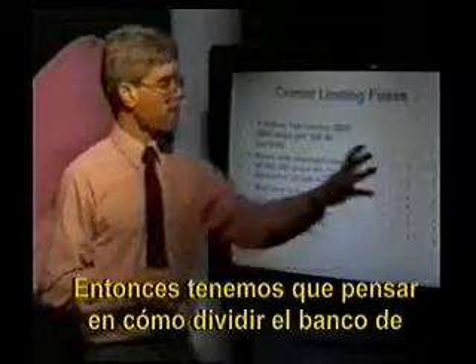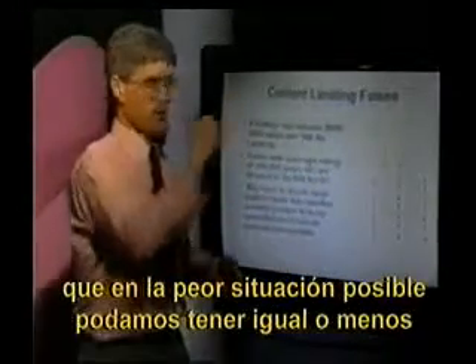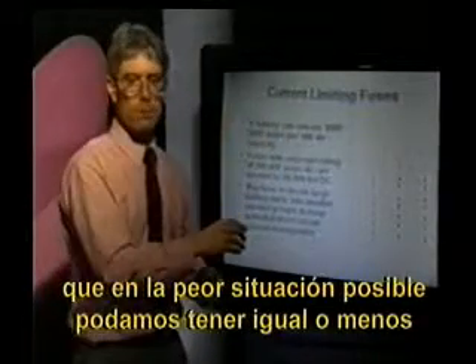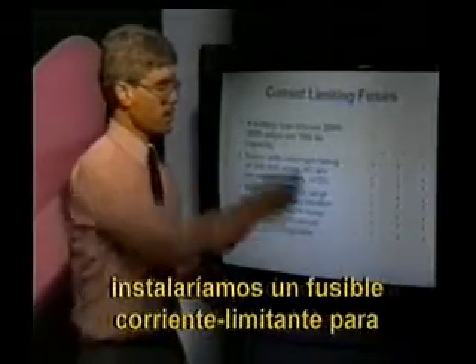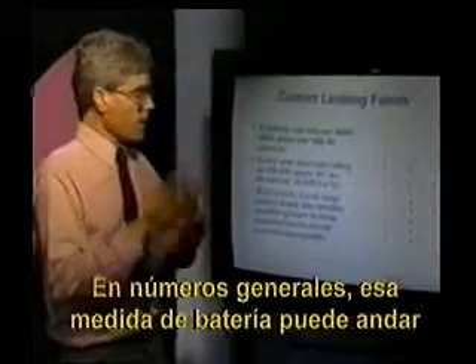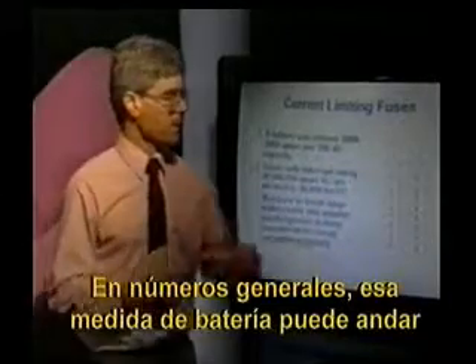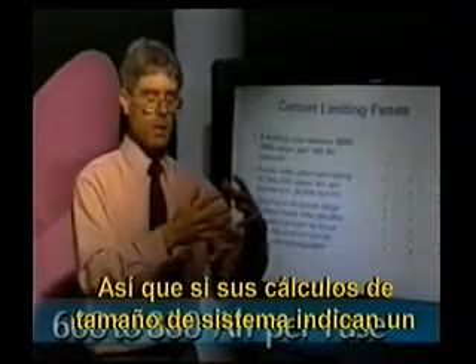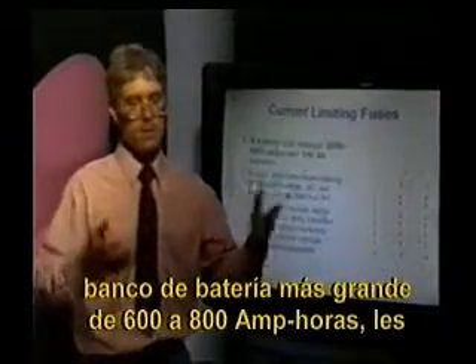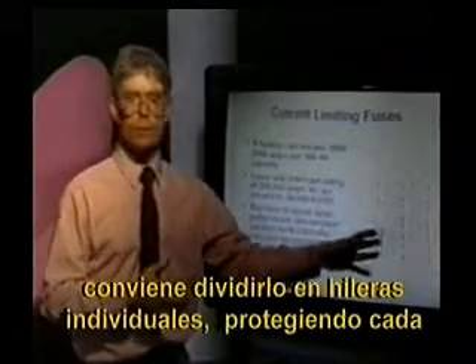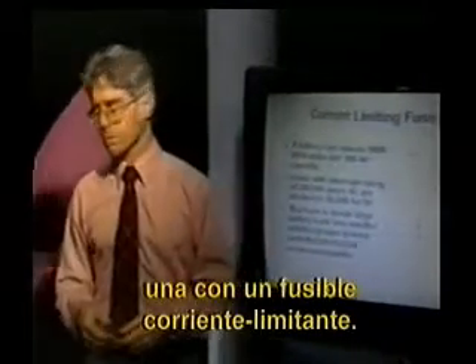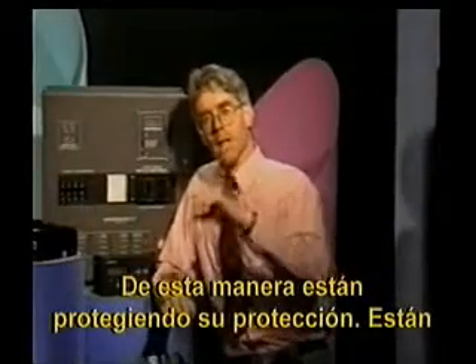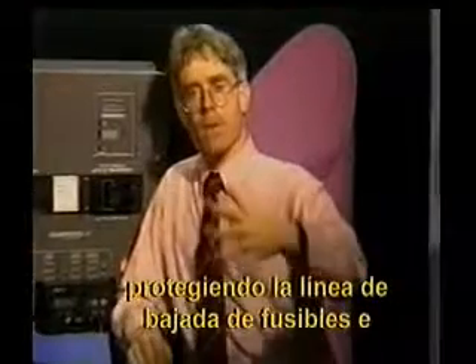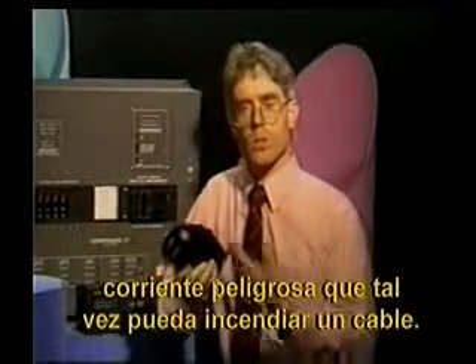So what we have to think about is how can we break our battery bank into small enough units so that under maybe the worst possible situation, we might have equal or less than 20,000 amps of current flowing from one string. Then we'd install one of these current-limiting fuses to break that much current. Roughly, in terms of general numbers, that size of battery bank might be roughly about 700 amp hours per battery bank. So if you find yourself with your system sizing calculations indicating a larger battery bank than 800 amp hours, you should consider breaking that into individual strings and protecting each one of those strings with a current-limiting fuse. In that way, you're, once again, protecting your protection. You're protecting the downline fuses and circuit breakers that might be in your system. Circuit breakers and fuses are rated for their ability to break current, to stop a dangerous current flow from perhaps catching a wire on fire.